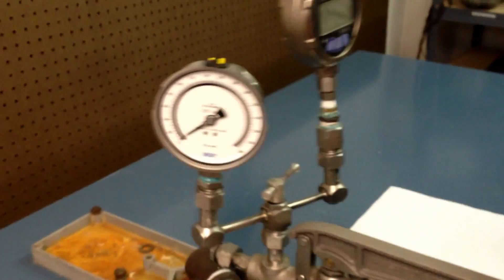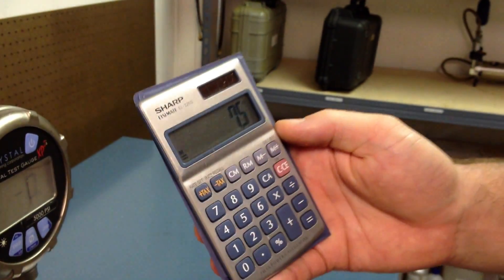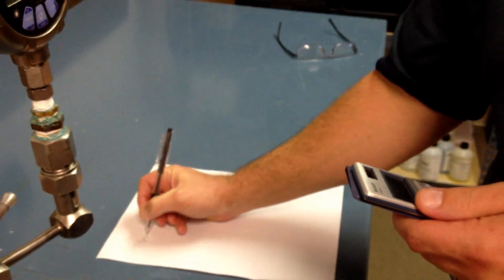So, if we're at 3,000 PSI times 0.25%, this can be plus or minus 7.5 PSI.